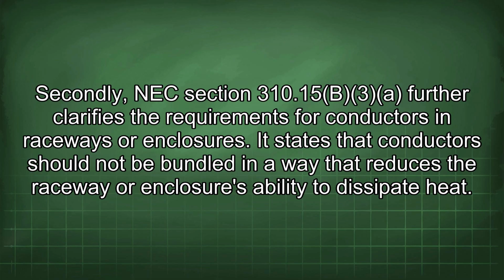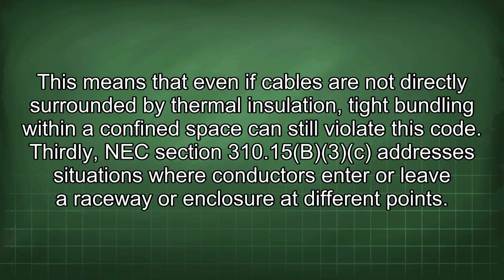Secondly, NEC Section 310.15(B)(3) further clarifies the requirements for conductors in raceways or enclosures. It states that conductors should not be bundled in a way that reduces the raceway or enclosure's ability to dissipate heat. This means that even if cables are not directly surrounded by thermal insulation, tight bundling within a confined space can still violate this code.